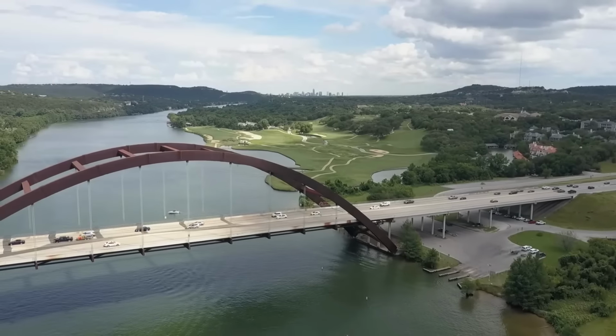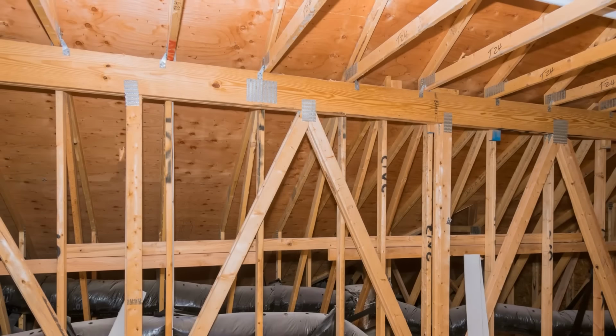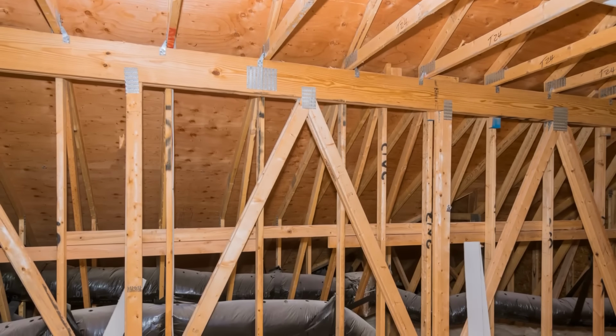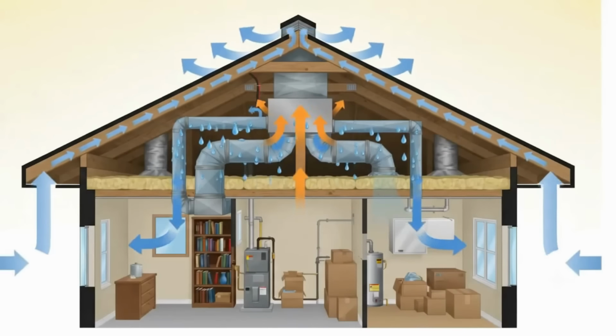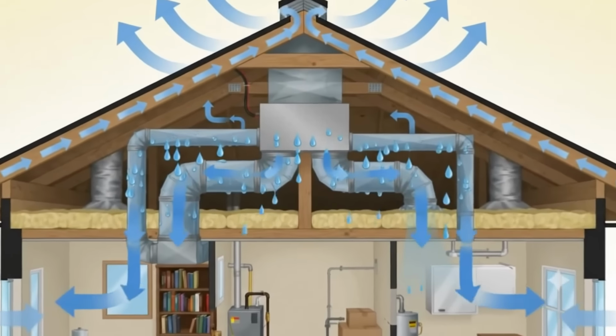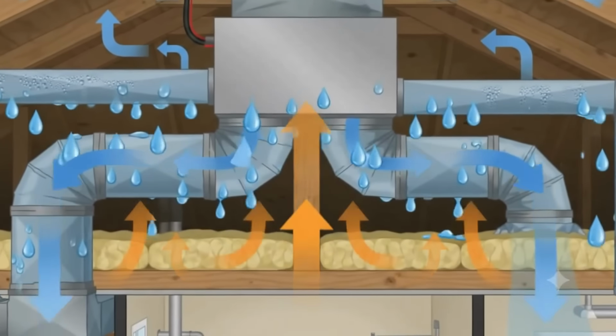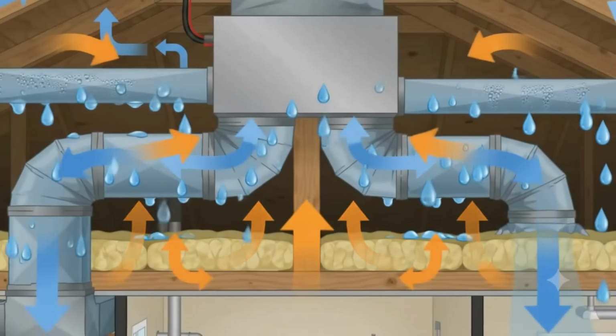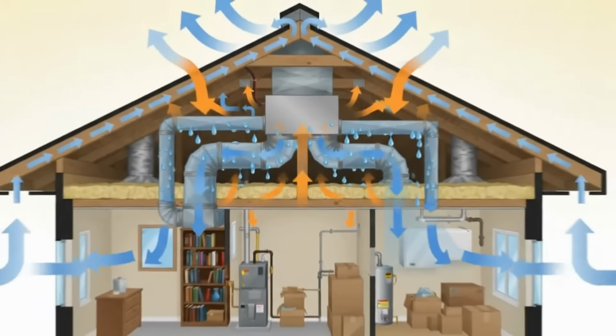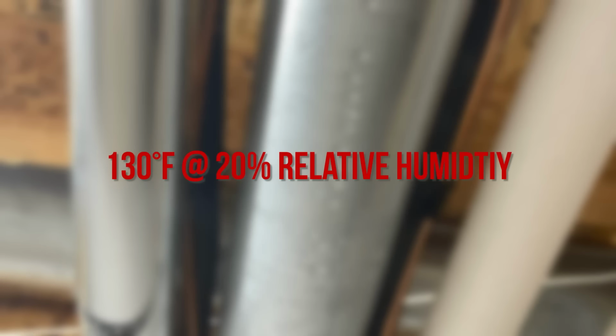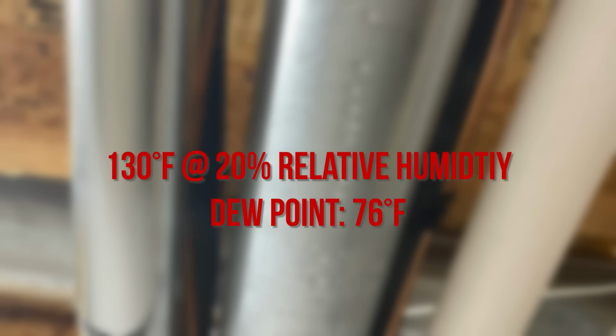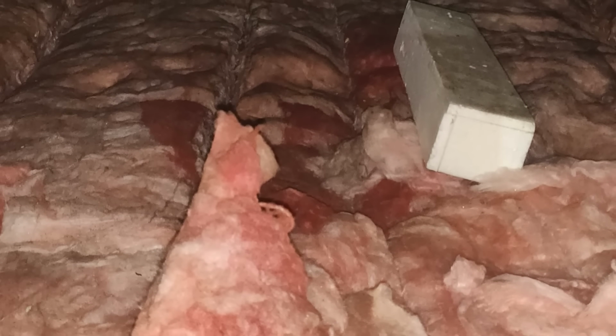In hot, humid, and mixed humid climates, the air inside the vented attic space is warm and humid, go figure. When that warm, humid air comes into contact with the cold surface of your ductwork or air handling unit, the air is rapidly chilled below its dew point, resulting in condensation. For example, if we have 130-degree air at 20% relative humidity, our dew point is going to be 76 degrees. This water drips onto your insulation and ceiling and satisfies the conditions that trigger mold growth.